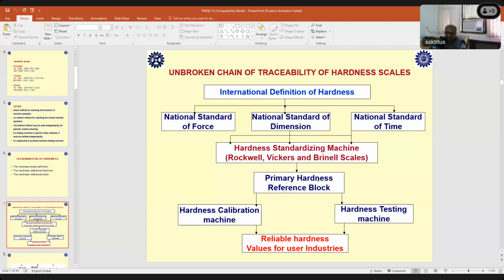And whenever you calibrate any block, any standard test piece, as per the procedure written in part 3, I have already mentioned to you that every standard has 3 parts. If you calibrate any hardness block as per part 3, then that block can be treated as a reference block. That is treated as a standard reference block. So that is again a standard which is used for calibrating several hardness calibration machines, testing machines, and all the working machines, everywhere it is used for calibrating the machines.